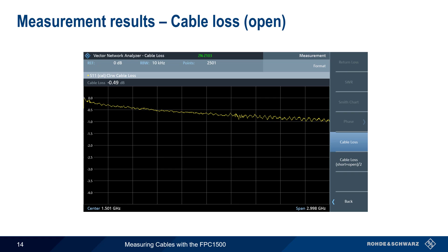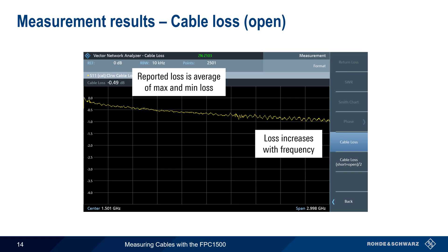Here's an example of measuring cable loss using only an open termination. We can easily see that loss increases with increasing frequency, which is typical for cable measurements. An average numerical value of cable loss over this frequency range, here 0.49 dB, is also automatically calculated and displayed.